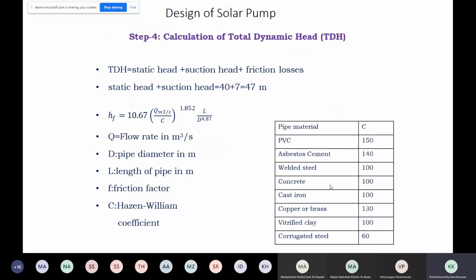You see here, the static head from the underground to our walking level, the ground level, is 40 meters. And from the ground level to my top floor, to my overhead tank above my head, 7 meters. 40 plus 7, 47. One more loss is when water flows through the pipe, there will be frictional losses. If you just feed the same amount, you will not get there. The speed of water flow will decrease due to friction. That also we should calculate.